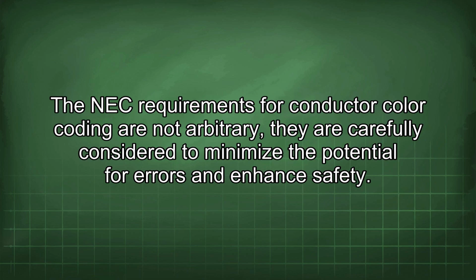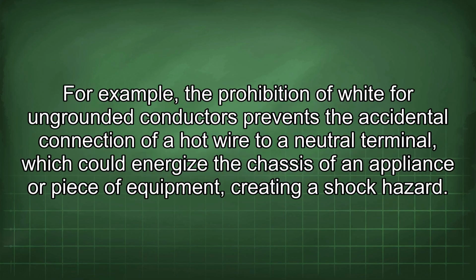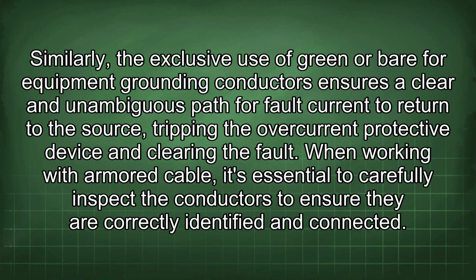The NEC requirements for conductor color coding are not arbitrary. They are carefully considered to minimize the potential for errors and enhance safety. For example, the prohibition of white for ungrounded conductors prevents the accidental connection of a hot wire to a neutral terminal, which could energize the chassis of an appliance or a piece of equipment, creating a shock hazard. Similarly, the exclusive use of green or bare for equipment grounding conductors ensures a clear and unambiguous path for fault current to return to the source, tripping the overcurrent protective device and clearing the fault.